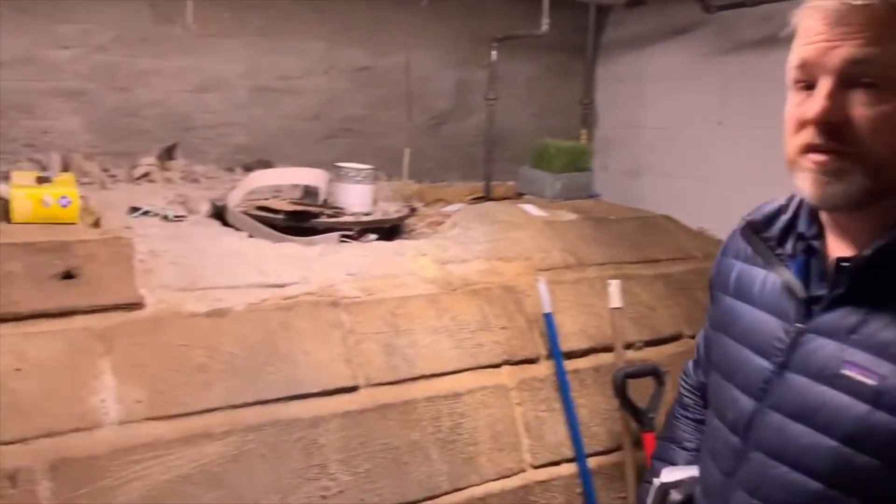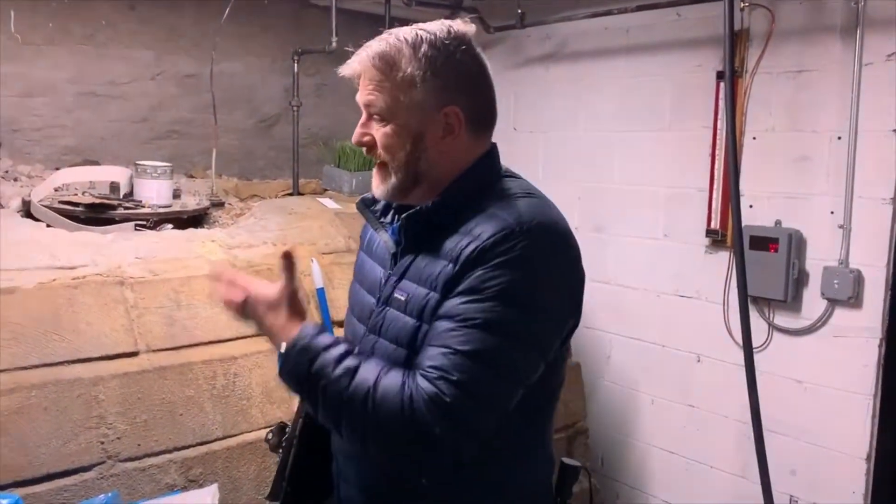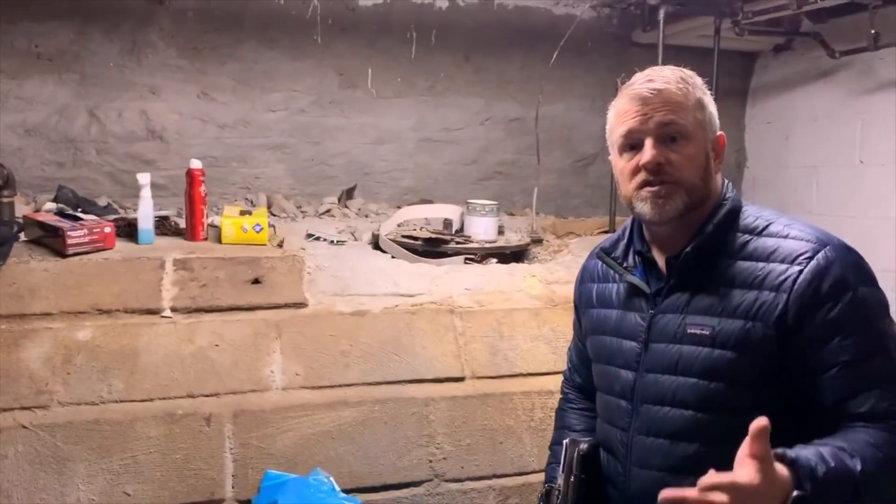So we know there's a tank in there. The problem is I can't view it — it's fire rated, covered with a CMU. Sometimes it's covered with concrete, sometimes it's insulated, and sometimes it's left exposed and the room itself is considered a fire-rated structure. In this case I can't really see a lot of it, so I'm going to ask the super: age, condition, issues, etc.